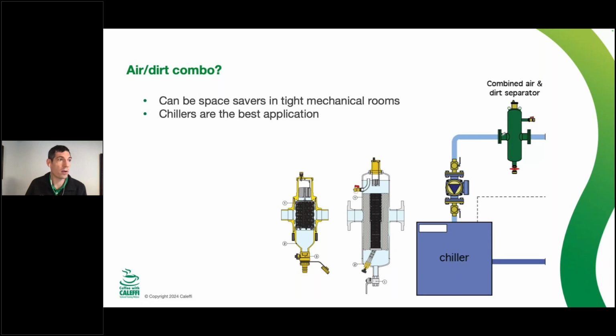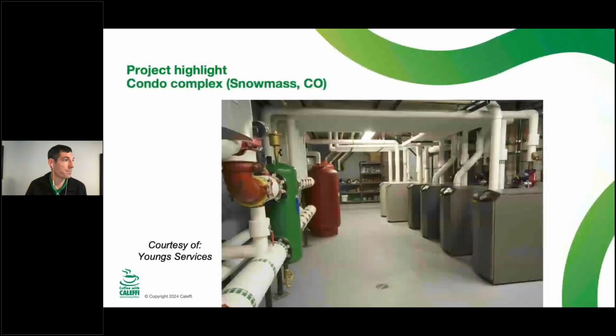But if this were a boiler, the air separator would be good on the hot point of the system, which would be on the outlet. The dirt separator, we want to catch it before it gets to the expensive stuff. So you can, in hydronic systems, use an air and dirt separator combo. It saves some space, saves some money on the job. But really, you have to pick if you want it to perform best as the air separator or the dirt separator, because it won't necessarily be in the same spot for a hot water hydronic system.